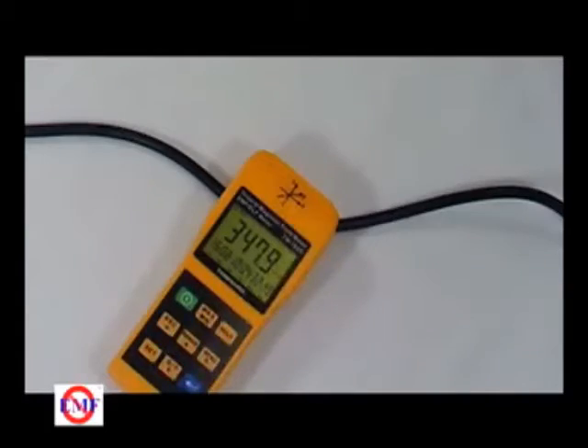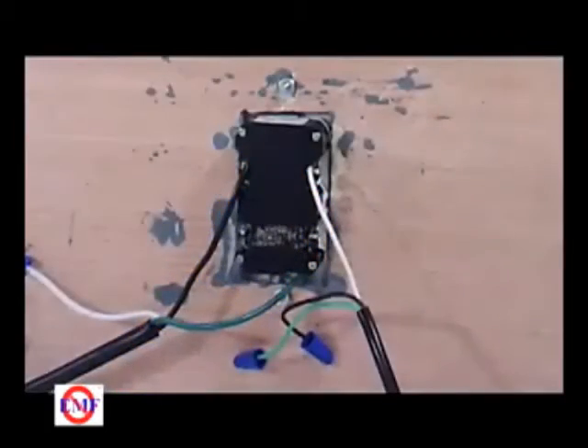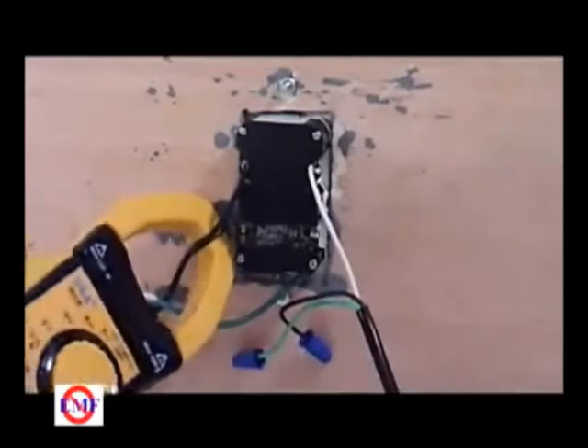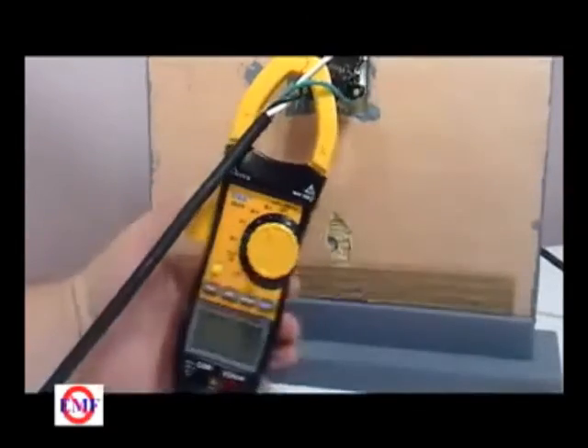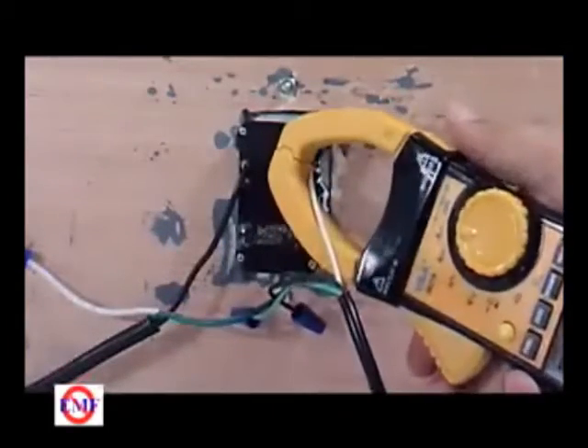The easiest way to find out if you have net current is to use a clamp-on ammeter. First, clamp around the black wire and record the current. Clamp around the white wire and record this current.